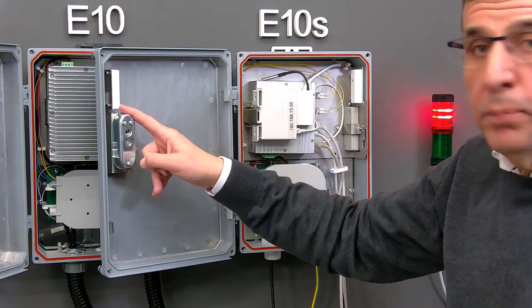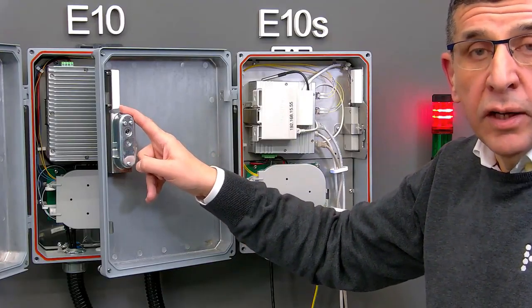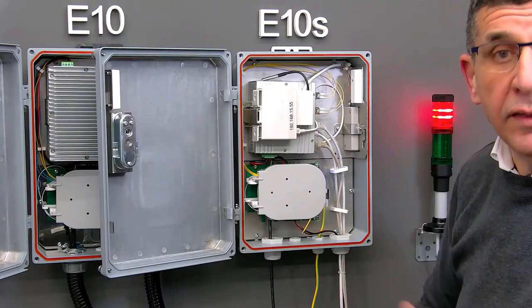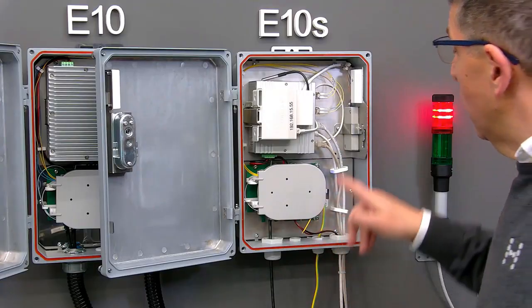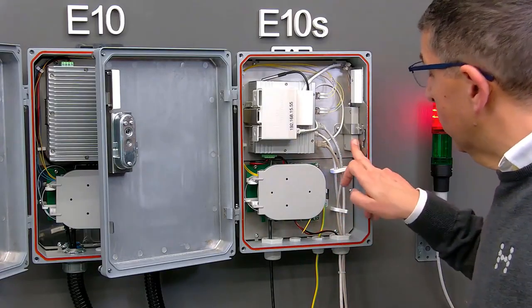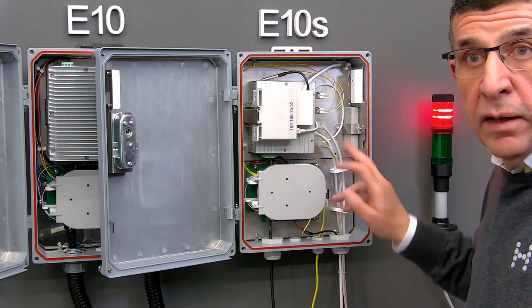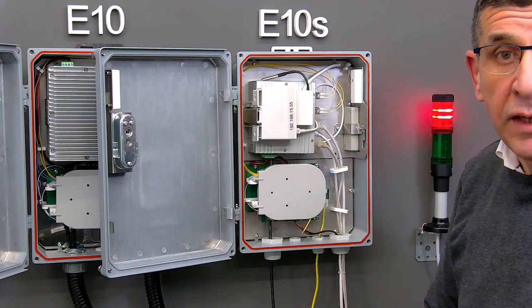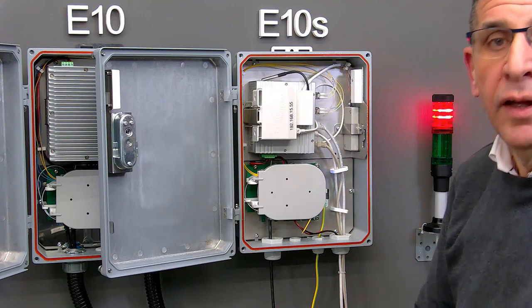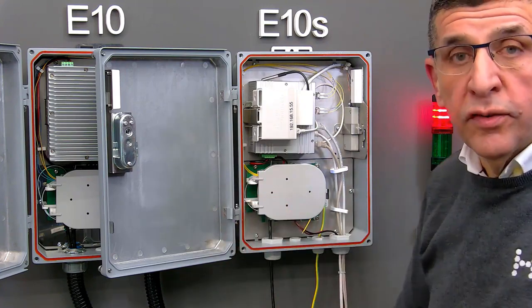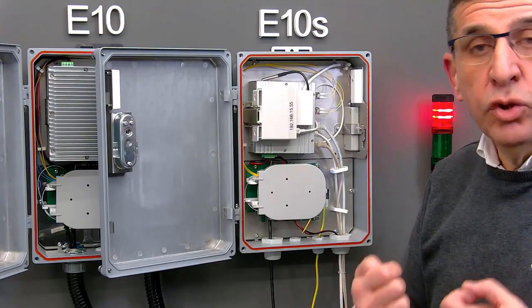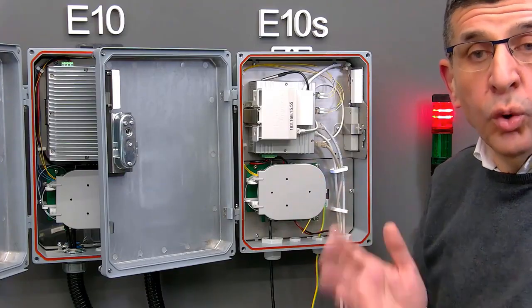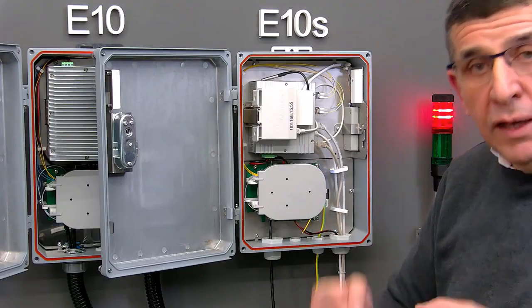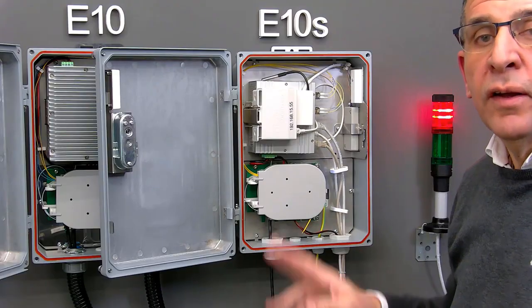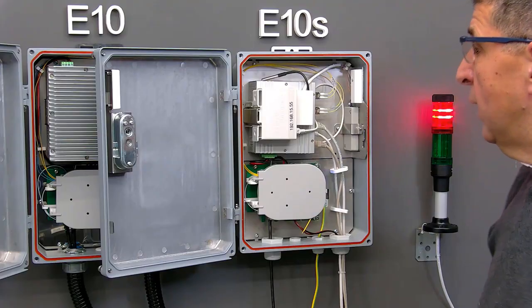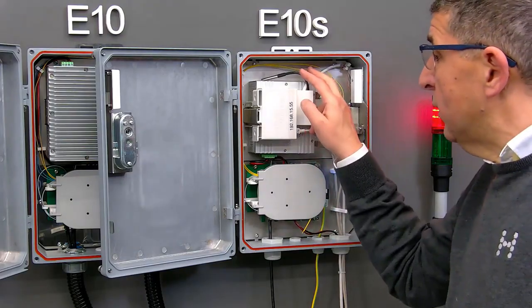We have also added a place to put in a magnetic sensor. This one is fitted with a grade 3 magnetic sensor. There is also a seismic sensor, and that gives an alarm if there is any intrusion or tampering with the cabinet. So even if the door is still locked, but somebody is trying to break in, saw the cabinet, bang on it, or even on the pole it's hanging on, you get an alarm from the seismic sensor. We also have added a temperature sensor.